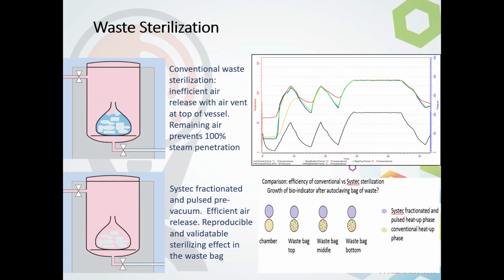Waste sterilization is going to be very similar as well, but we have different things that we have to worry about. With conventional waste sterilization, again, we have water inside of the unit that it's going to heat up. We also know that we have some water components inside of the bag as well. But when we start heating that, all that it actually does if we don't pull a pre-vacuum is compress the air into the bag. So if you were to put a biological indicator directly in the center of one of those waste bags that you're putting into your autoclave, or tape that waste bag up, which I see folks do all the time, they tape the bag up and stick it down into the autoclave, there's absolutely no way that we can get steam penetration into the unit if all we've done is completely sealed the bag.